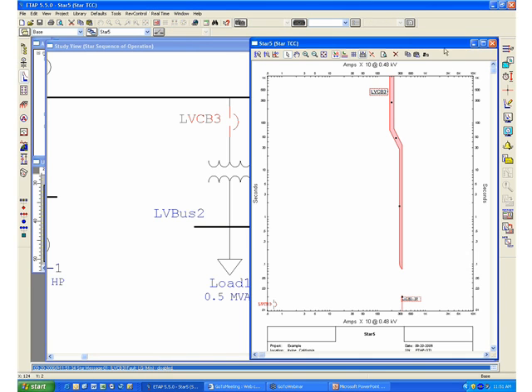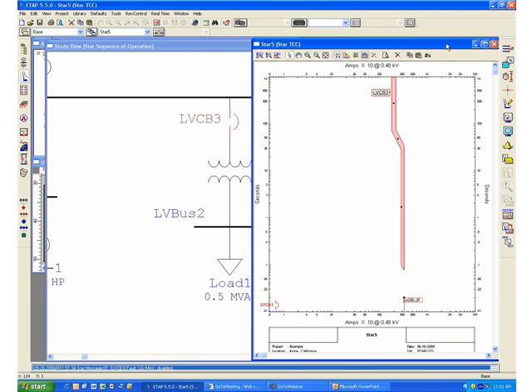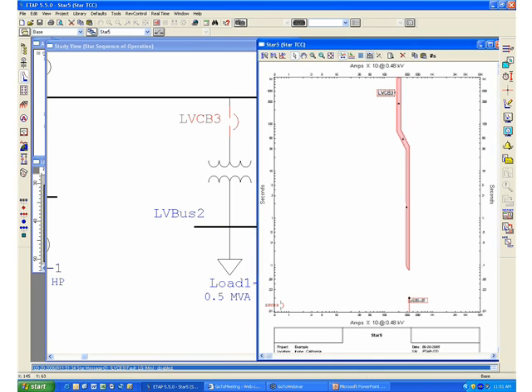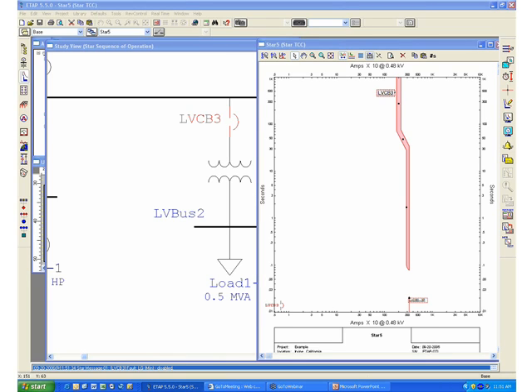At this point, you can see that the program has determined that the low voltage circuit breaker will trip at a very high time, approximately 37 seconds, and it actually has fallen off the instantaneous setting of this device.